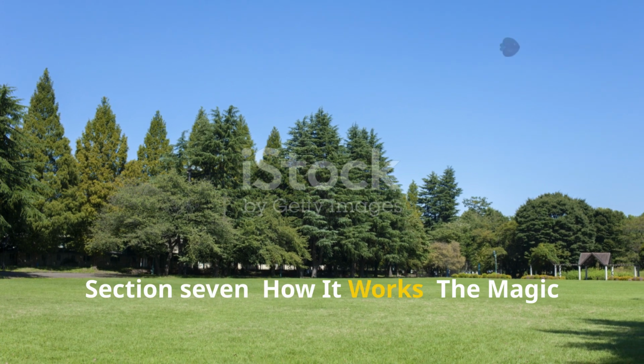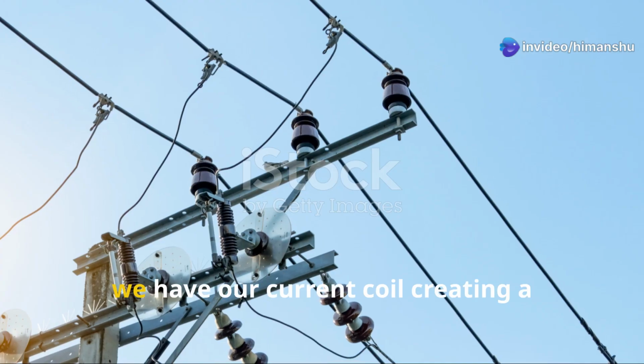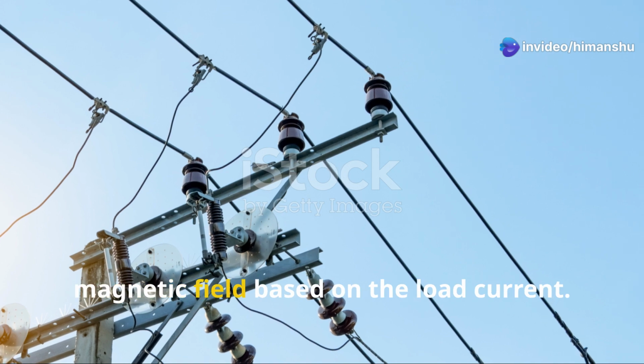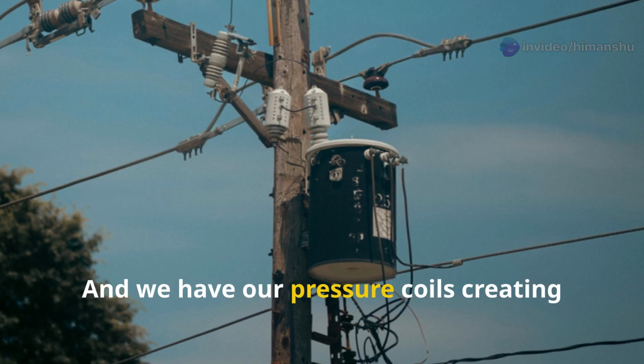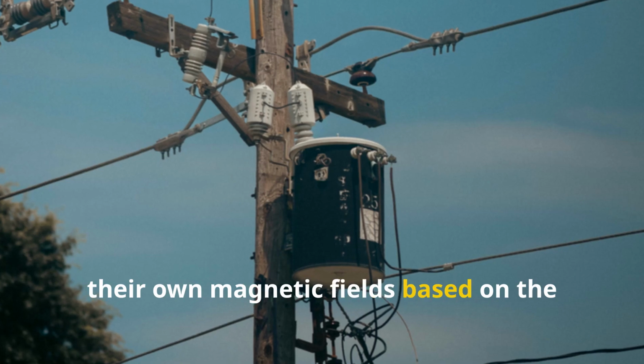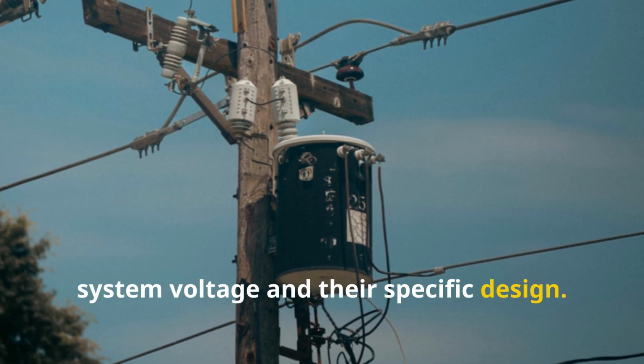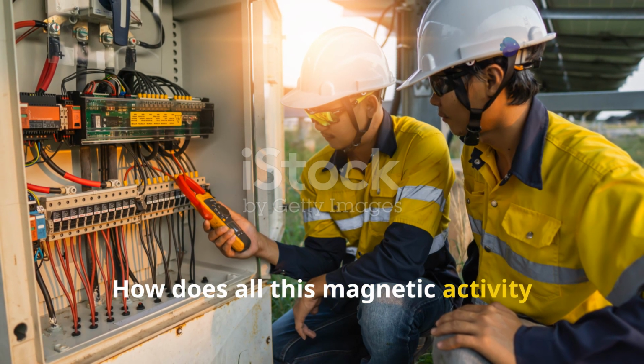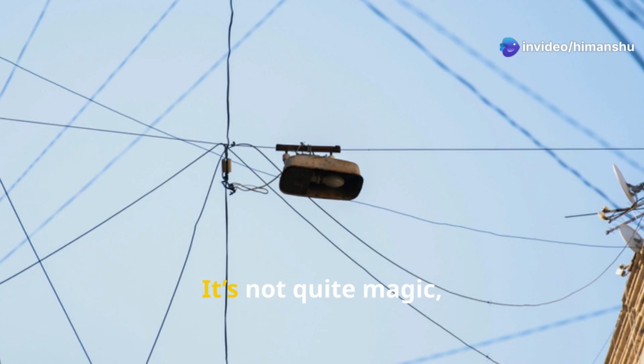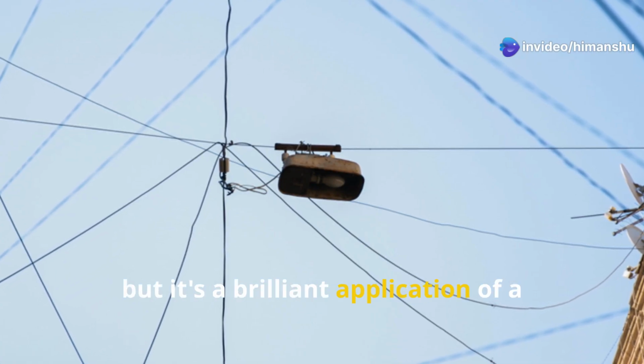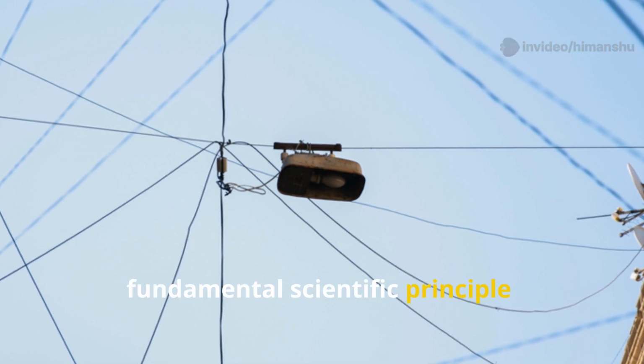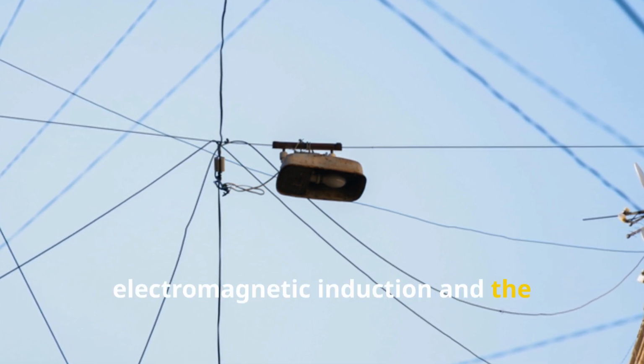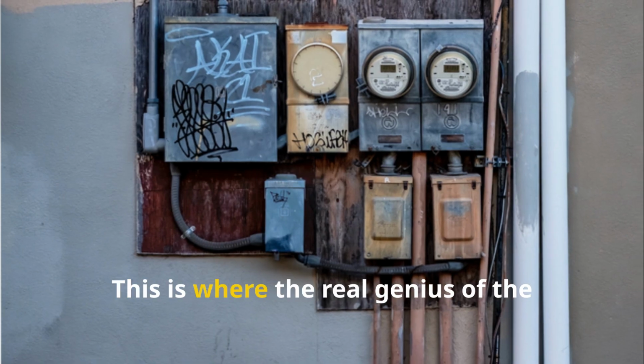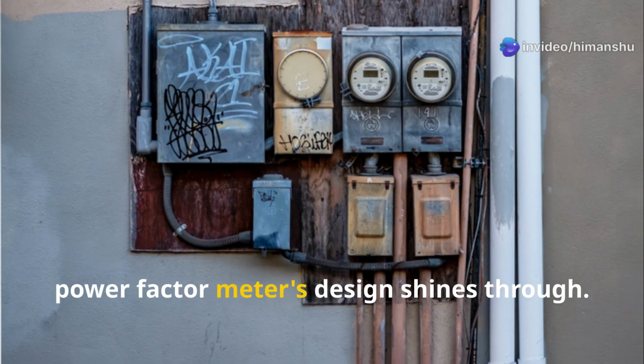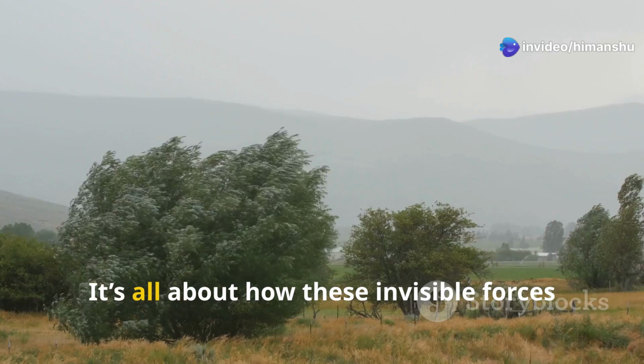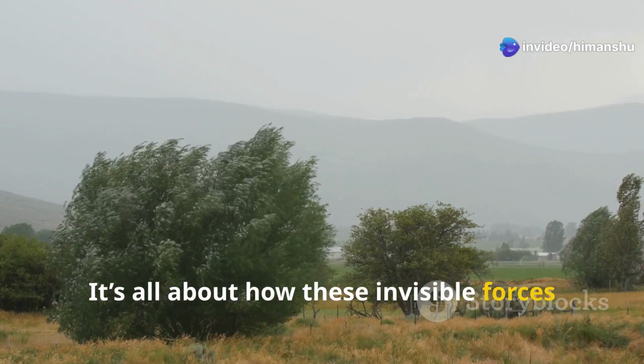Section 7, how it works, the magic of magnetism. So we have our current coil creating a magnetic field based on the load current, and we have our pressure coils creating their own magnetic fields based on the system voltage and their specific design. How does all this magnetic activity actually tell us the power factor? It's not quite magic, but it's a brilliant application of a fundamental scientific principle: electromagnetic induction and the interaction of magnetic fields. This is where the real genius of the power factor meter's design shines through. It's all about how these invisible forces influence each other.